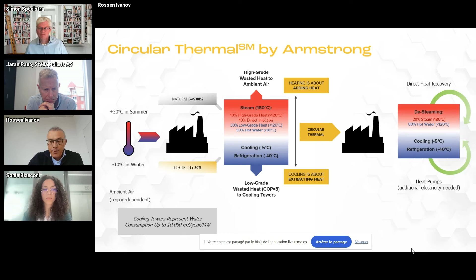Direct heat recovery always comes before heat pumps, and this is shown through the pinch methodology. The pinch methodology has been around for more than 40-50 years. This is how very energy-intensive industries such as refining and chemical plants are designed. The goal there is, instead of having energy use for cooling and energy use for heating in parallel, these streams are overlapped, and the gray zone shows the area where temperatures are overlapping, so it is possible to implement direct heat recovery using just a heat exchanger to recover high-grade heat in order to preheat something at a lower temperature. This is going to minimize the quantity of energy needed for cooling and heating. However, this energy is still required. Using heat pumps, doing this difficult work of recovering low-grade waste heat at the lowest temperature and bringing it up to the highest temperature needed in the plant, allows us to further decrease the overall primary energy.